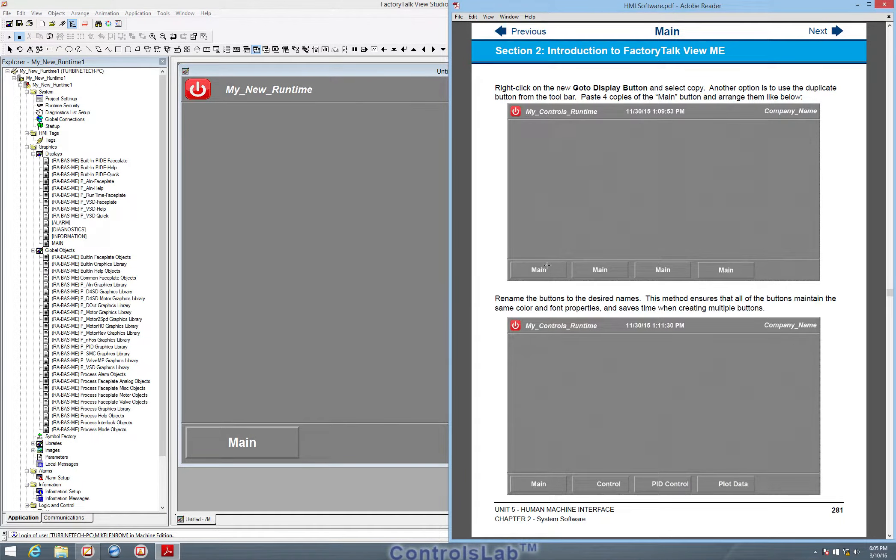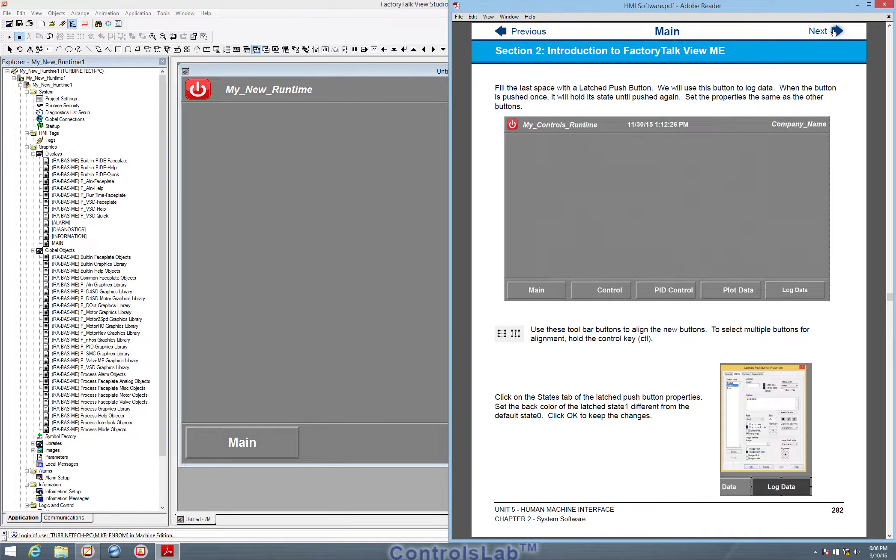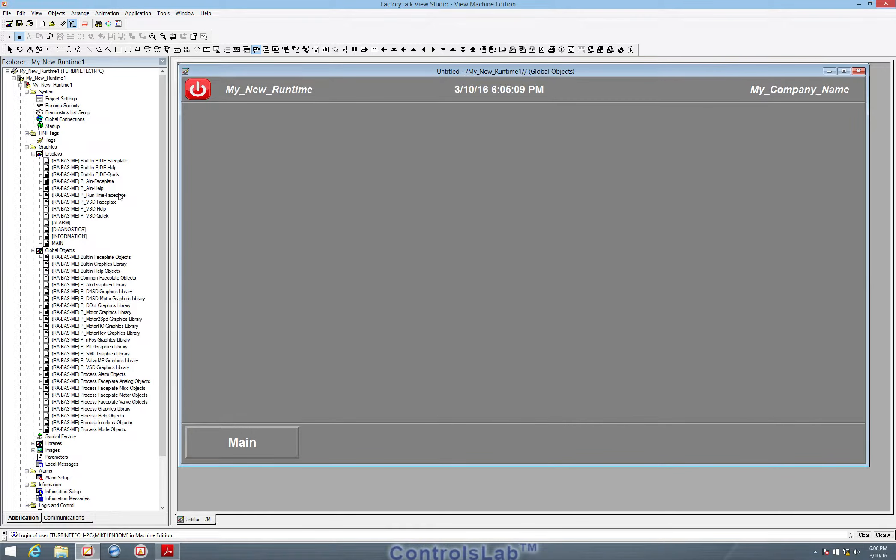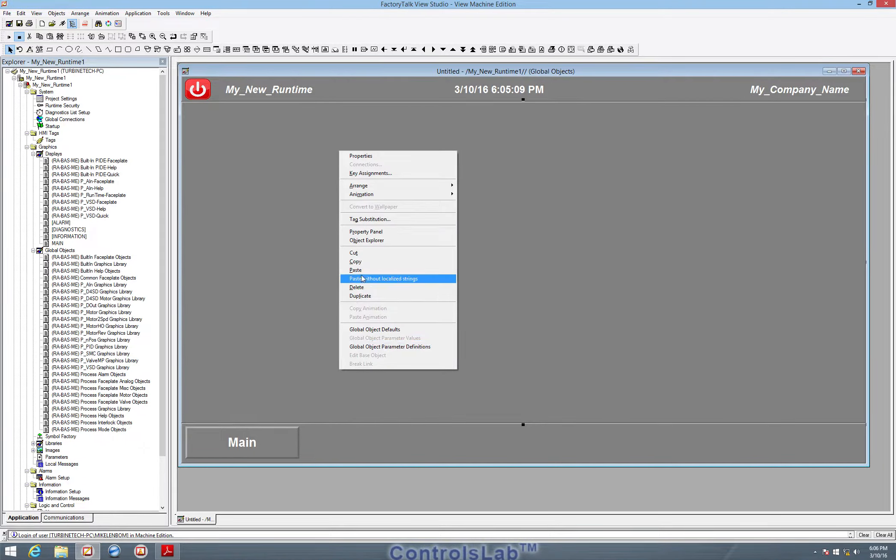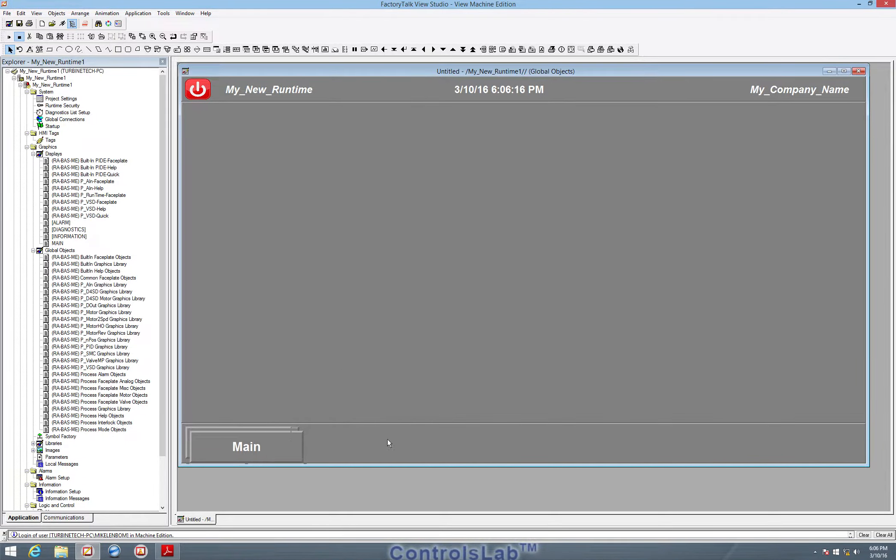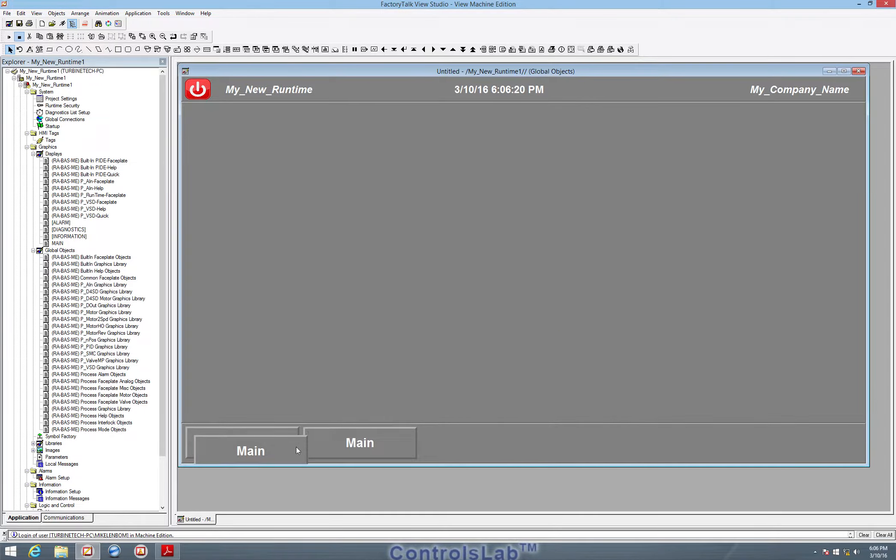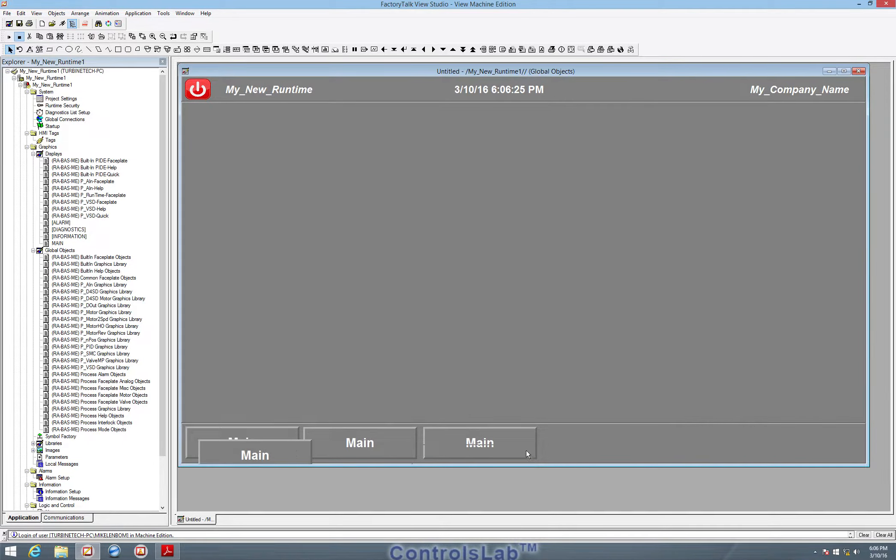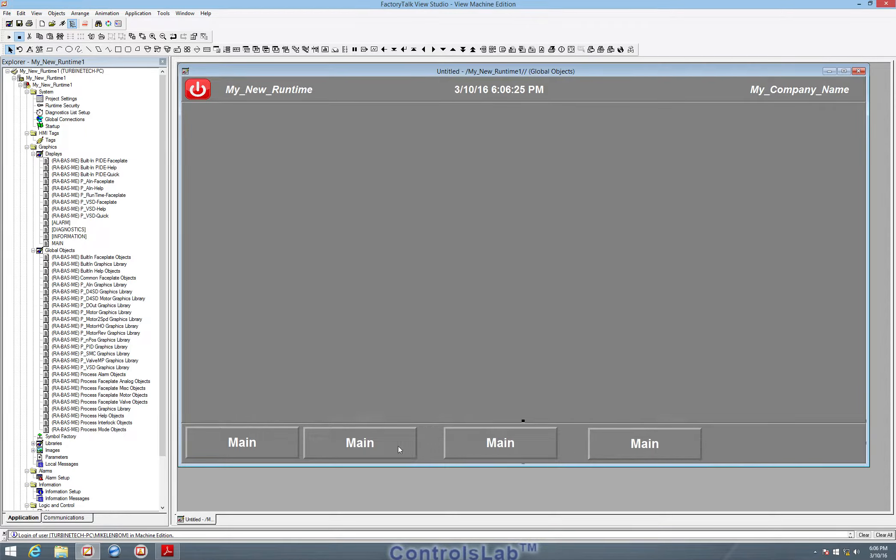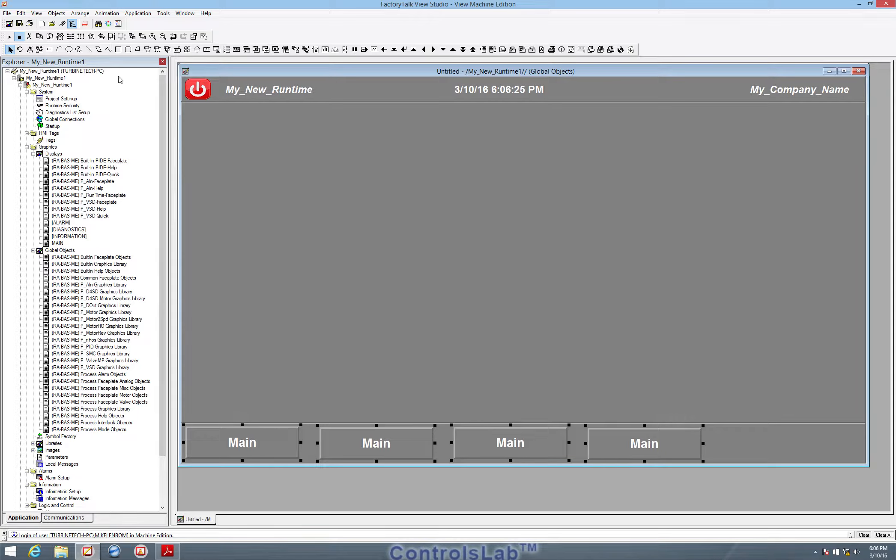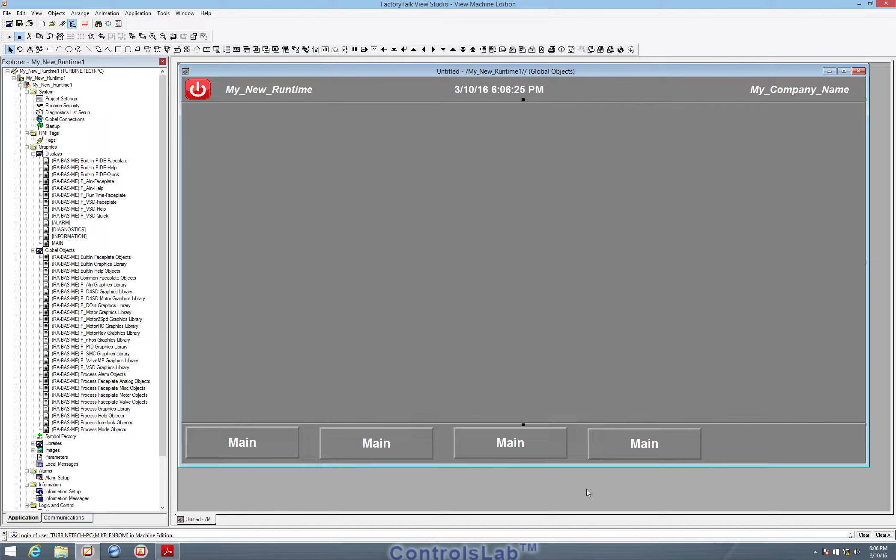Now we basically have the same go to display button for each of the different controls. So I'm just going to take that main button, copy it, and paste it three more times. And we can select each item by holding the control key. And when we select the items, we have the ability to space them horizontally. That'll even the horizontal spacing. And we can also space them vertically, which will match them all in line vertically. So we have all of our buttons there.